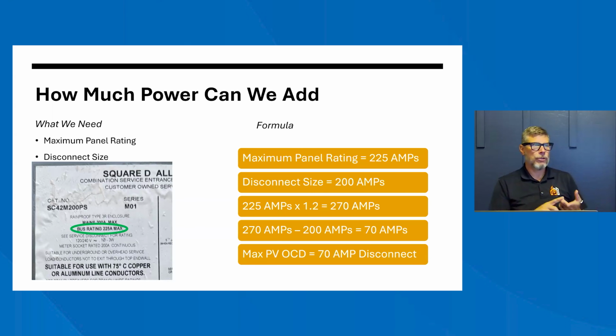The way we're going to do that is through this formula. You're going to take your maximum panel rating, in this case 225 amps, and we're going to use your main disconnect, which we're saying is going to be 200 amps. We develop our 120%, which is 270. We're then going to subtract our main disconnect, 200 amps, from the 270, which is going to leave us with, simple math, 70 amps. So that tells us that our solar array can have a maximum overcurrent protection of 70 amps. So a 70 amp disconnect is what we can see in the panel. So that's actually a relatively large array. That would probably power a whole house. So that's how we determine what we can put into the panel.